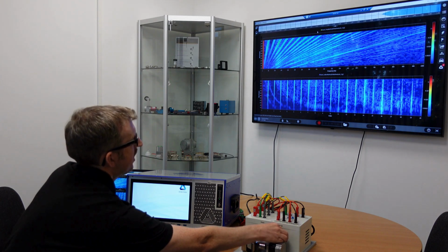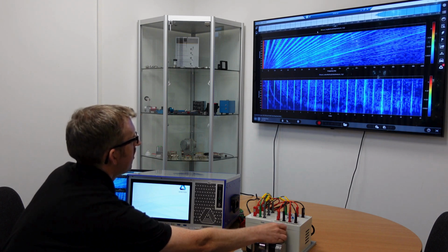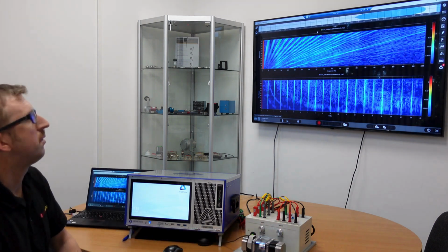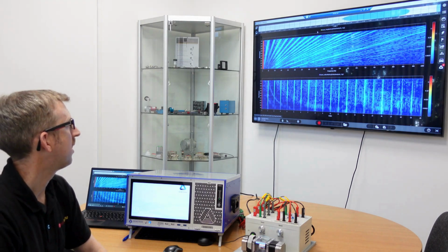And we reach maximum speed, and then we can shut the motor off. And here we can see the dominant frequency on the left hand side of the charts is the first order, but then we can also break out into higher orders and start to investigate the vibration data in more detail.